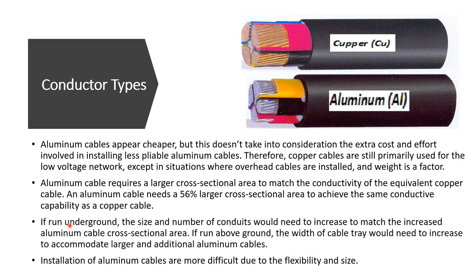When running aluminum cables underground in a low voltage network, two problems arise: first, the size and number of conduits required increases because aluminum cables have a larger cross-sectional area; second, above-ground installations require larger cable trays to accommodate the bigger aluminum cables. That is why copper cables are preferred in the low voltage network.